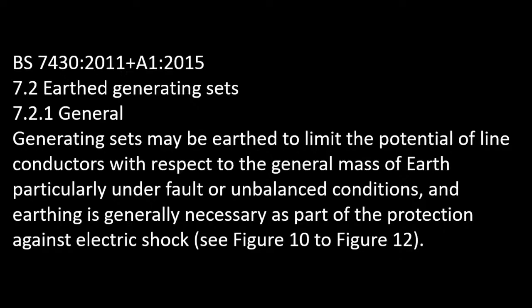Yeah, smaller. So yeah, and again, within that same standard 7430, it actually tells us that the purpose of this earth electrode isn't to provide an earth fault path. That's not its main purpose. If we look at it within that standard, it says that it's earthed to limit the potential of the line conductors with respect to the general mass of Earth, particularly under fault or unbalanced conditions. So it really is to stop it being a floating generator and to pull it down for a couple of reasons. The main one being that now we've got a very low resistance between the earthing arrangement of the generator and true earth, so we're not going to introduce large potentials if users of the installation are in touch with both. So yeah, it's not creating a TT.